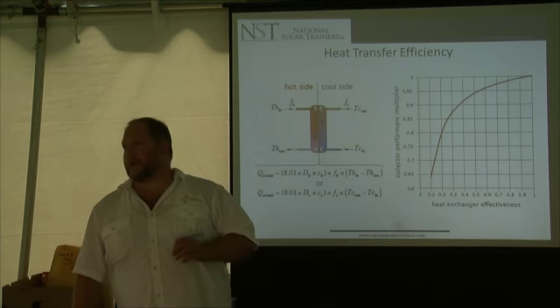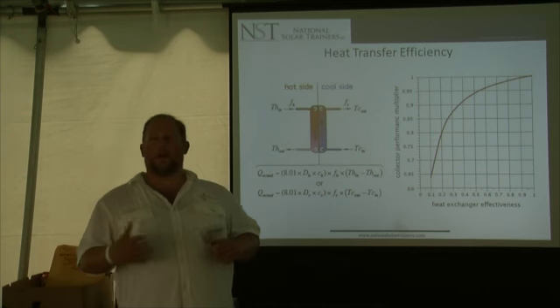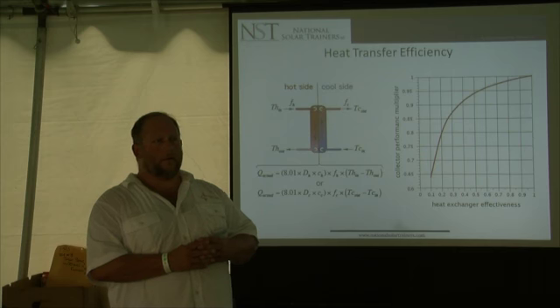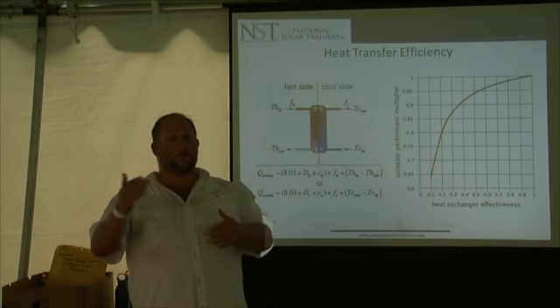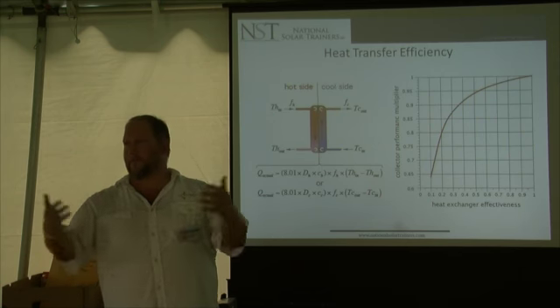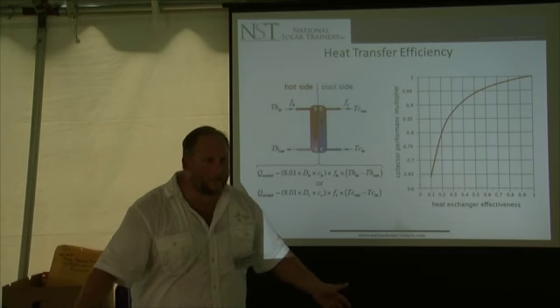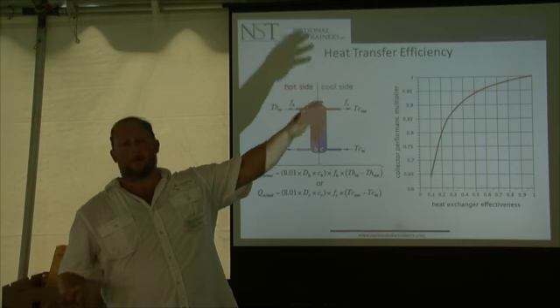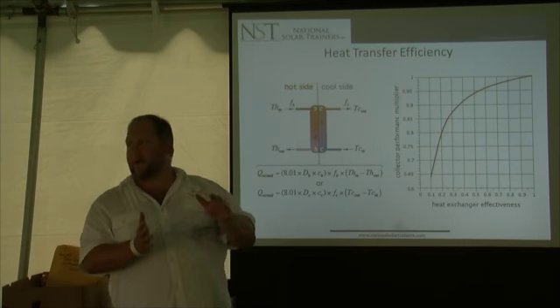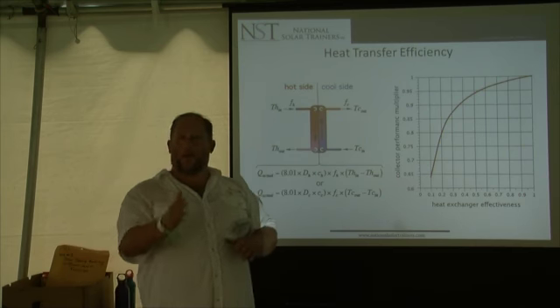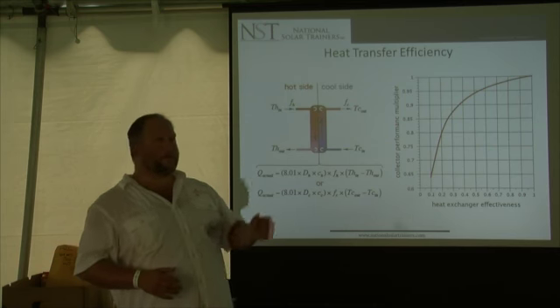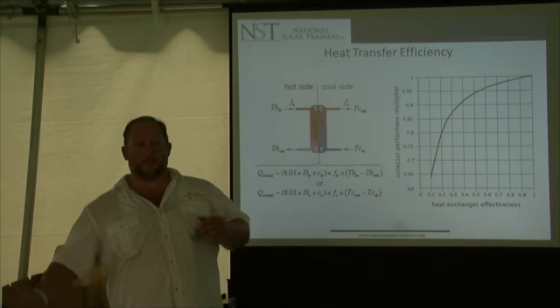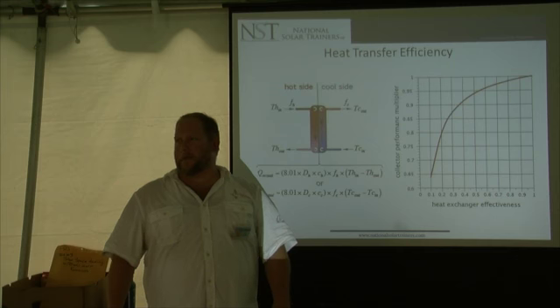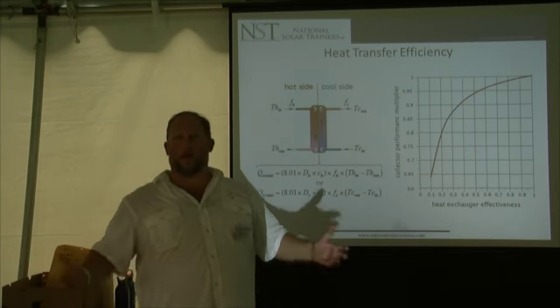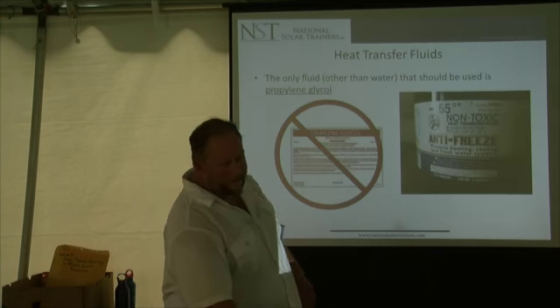One thing I want to point out about heat exchangers is the second law of thermodynamics is what's applied to this. Because every time you transfer energy, what happens to it? Less and less and less and less and less. The same principle. If I apply a heat exchanger between my solar loop and my domestic loop, that heat exchanger is a point of loss. We call that a performance penalty. Well, if I have one heat exchanger, I'm going to lose 5%. If I have 2 heat exchangers, I lose 10%. So every heat exchanger you have in the system causes you to lose performance. Okay, so you want a design system that had the least amount of heat exchangers.